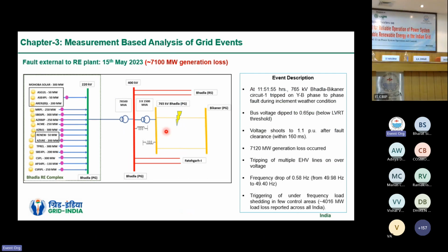A similar event we also witnessed on 15th of May 2023, where there was a fault external to the RE plants. This fault was in the transmission network. A phase-to-phase fault took place in the Bhadla Bikaner 765 kV line. The voltage dipped to 0.65 per unit, and then immediately after fault clearance, the voltage went above the specified limits, and again some IBRs went into HVRT mode, and subsequently, due to the reduction in line loadings, the lines also tripped on over voltage. The phenomenon is very similar to what was observed during the 11th August event.